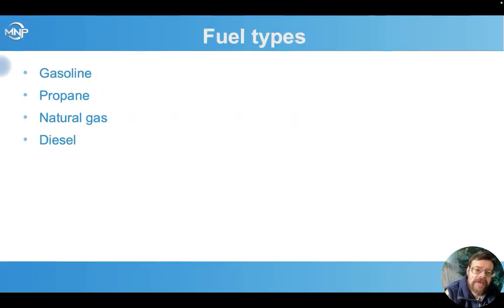Fuel types, we've got gasoline, propane, natural gas, and diesel. Typically, I don't use a lot of gasoline ones just because of the size. And like I said, once we're looking at the 12 to 15 kilowatt size, we're usually looking at a permanent pad mounted one, and those are generally propane, natural gas, or diesel. Most off-grid situations don't have natural gas available. If they do, great, but most of them don't. So propane is really the most common fuel that we use.